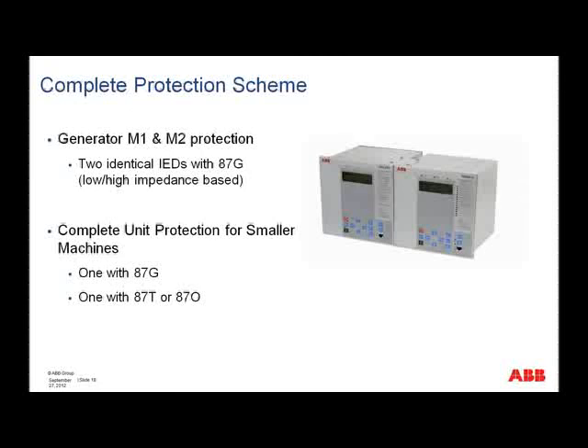So then if we want to make a complete main 1 and main 2 protection scheme, we could do that with two identical IEDs, each IED with an 87G, or of course it would be possible for smaller units really to have one IED with 87G and the other IED either with an 87T to protect then just the step-up transformer, or really with the same function but implemented as an 87O, which would then include both the generator and the transformer.